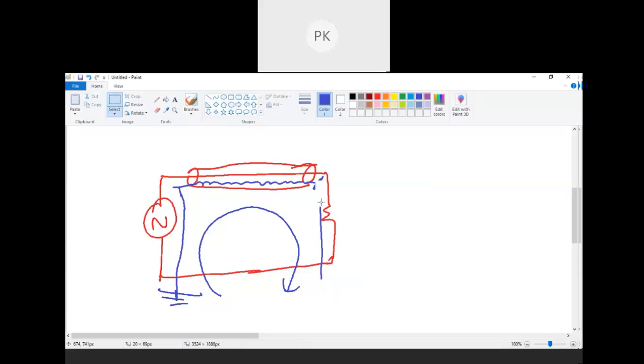Now if this is a three core cable, then what will happen? You have all three phases, R, Y, B. Because of all three phases, the induced voltage in the armor will be almost negligible and you will not have this circulating current. So circulating current is a problem only in case of single core cable.